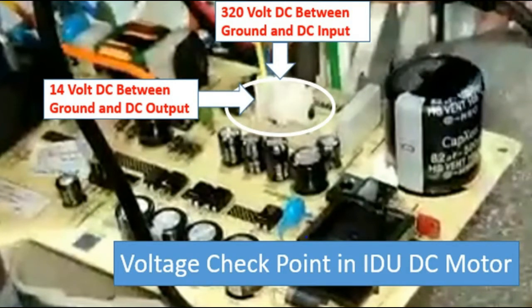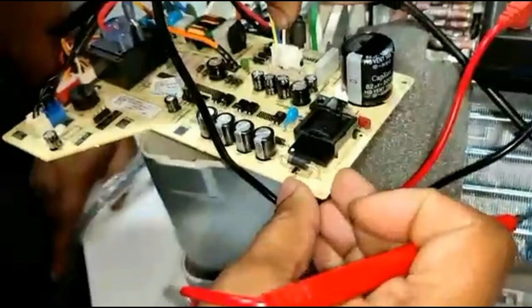If the split air conditioner is fitted with a DC IDU fan motor, then for checking the DC fan motor, we have to check the input voltage, which should be 320 or more DC voltage, and the output voltage between ground pin and output pin, which has to be 14 volt DC. For this, you can also watch my video on how to check DC motors. I have explained in detail in that video. For the IDU display, we can check at the connector of our display. There also it has to be 5 volt DC.